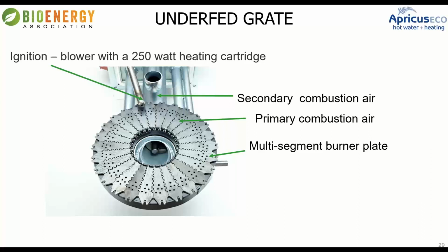So that's a really important thing to understand. Heat pumps are really efficient, but you're going to get a COP of about 3 or 4. A pellet boiler, if we look at energy in, energy out, from an electricity point of view, just because of course there's energy in the pellets, but from an electricity point of view, we've got a COP of 260, more or less. I hope it makes sense.